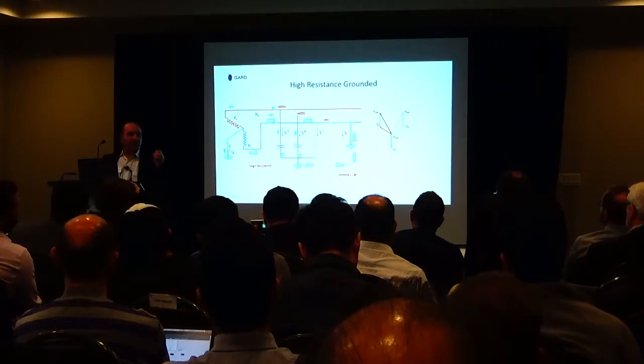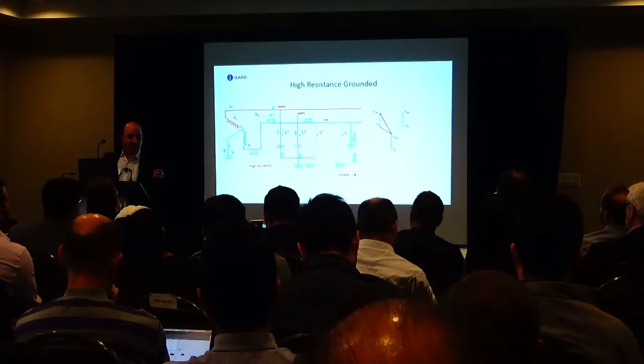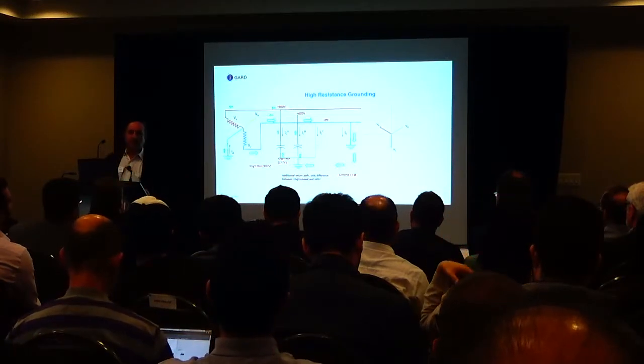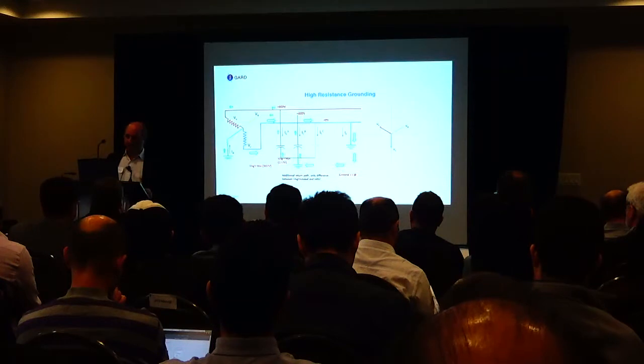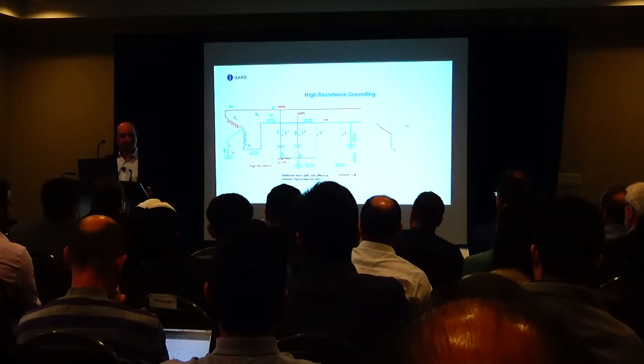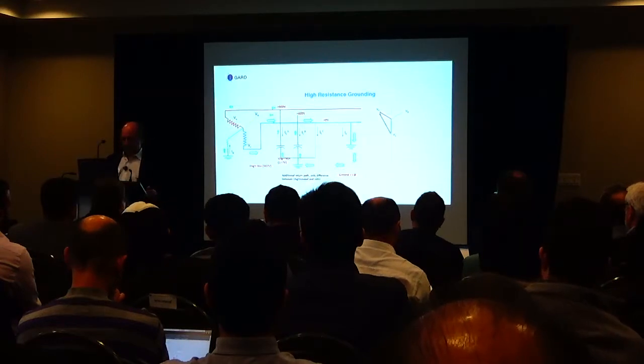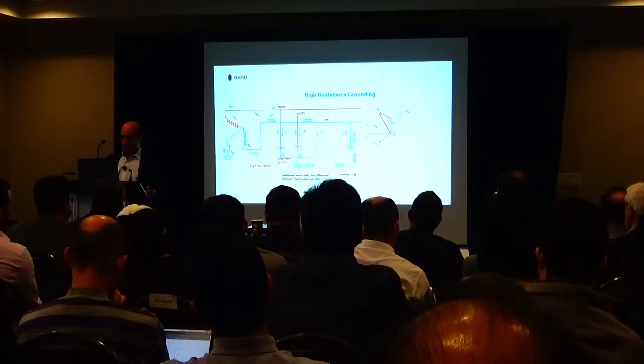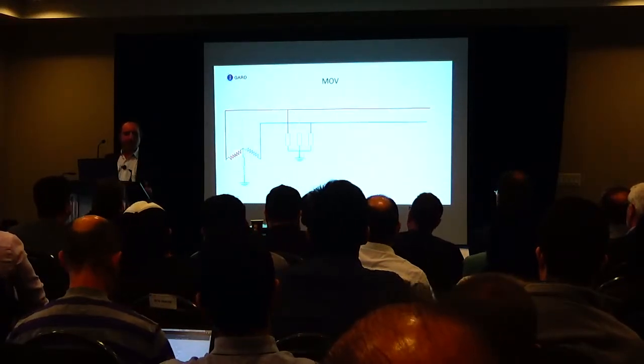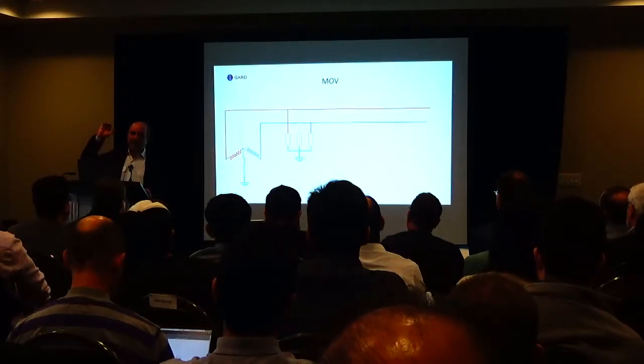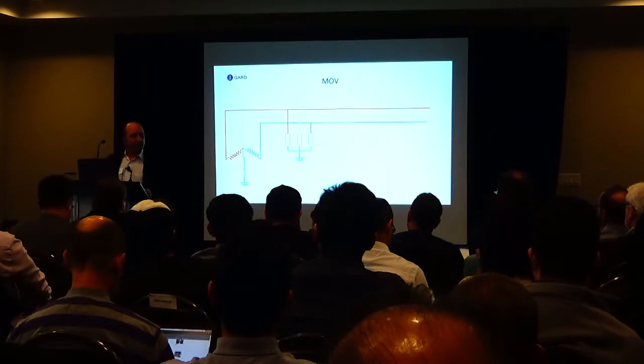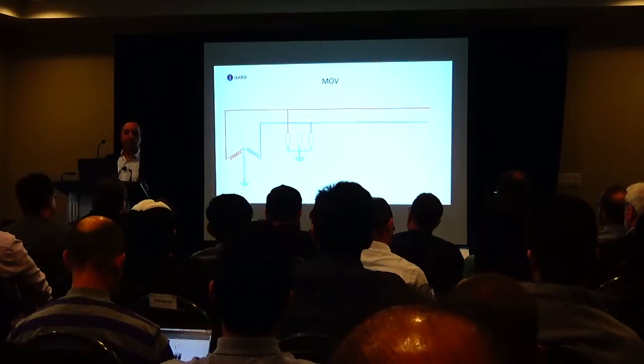The other school of thought is, remember, the line to ground potential shifts when you have a single phase to ground fault. The faulted phase to ground is 0 volts. The unfaulted phases to ground are at the full line-to-line potential. When you have line-to-line potential on two of the phases, you're measuring 600 volts, and 0 volts on the third phase, which is faulted. You have a ground fault, and that neutral shifts. So part of the problem when you have that neutral shift, and the unfaulted phases elevate to the full line-to-line potential with respect to ground, is that you have to watch out for SPDs, surge protective devices.